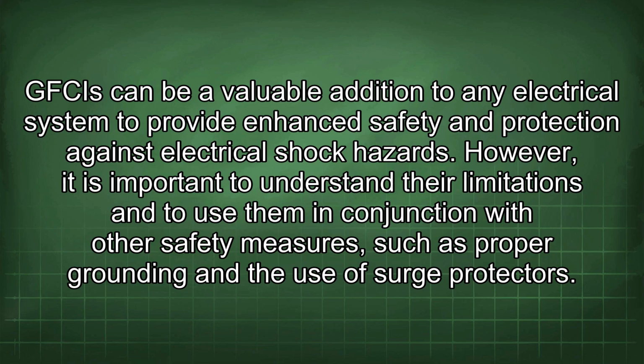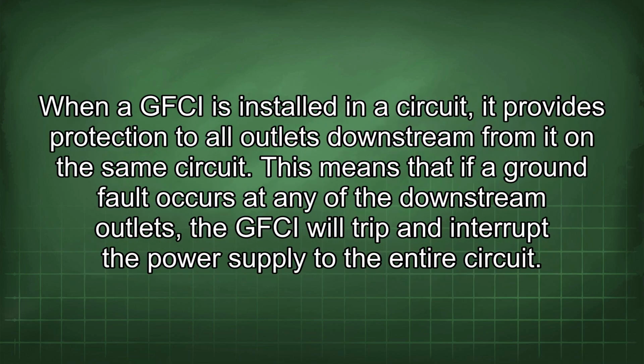GFCIs can be a valuable addition to any electrical system to provide enhanced safety and protection against electrical shock hazards. However, it is important to understand their limitations and to use them in conjunction with other safety measures such as proper grounding and the use of surge protectors. When a GFCI is installed in a circuit, it provides protection to all outlets downstream from it on the same circuit. This means that if a ground fault occurs at any of the downstream outlets, the GFCI will trip and interrupt the power supply to the entire circuit.